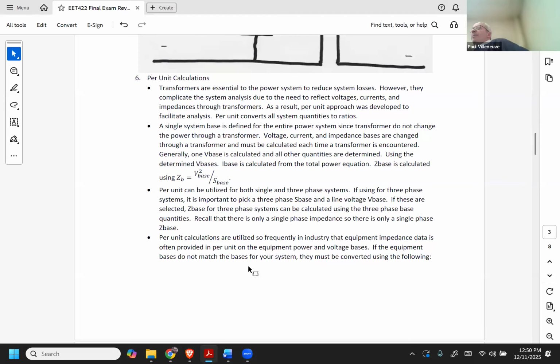Remember the rules about doing per unit: pick S base, and only one S base. Pick one and only one V base. The difference is I've only got one S base for the entire system, but for V base, I have to convert it through all the transformers, stepping it up or down. Every time I go through a transformer, I have a different zone or region where that V base exists. Once I have that, I can calculate the Z base in those regions just by using V base squared over S base, and I'm good to go - I can start converting and calculating everything I need.